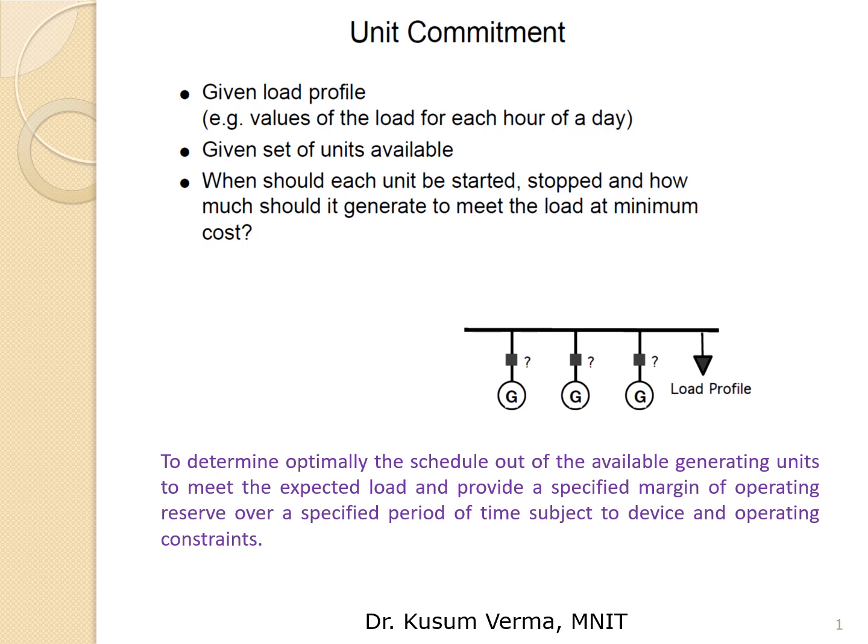Now the problem with committing units is deciding which to leave online, considering the economics also, because if only those units which are cheaper are committed, then there will be a lot of saving of money. And we can decommit those units which are not needed. Decommit means we can turn off those units which are not needed to meet the specified load demand for a given period of time. Now because the load is varying continuously with time, there is a need to calculate the optimum combination of units over the given period of time.